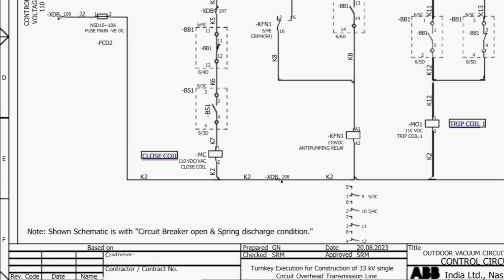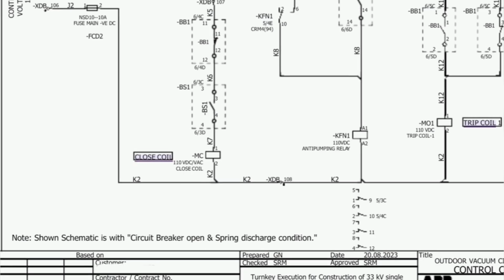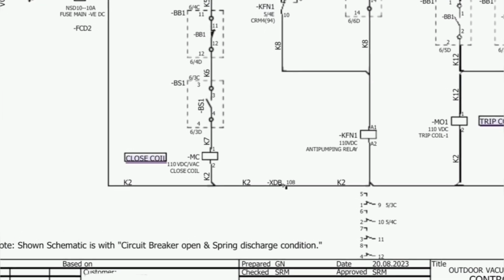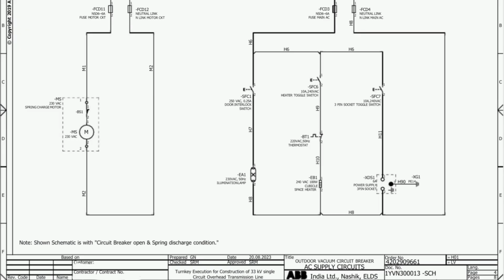Always study the drawing with the circuit breaker in the open position and the closing spring discharged. Keep in mind that terminal numbers and wiring arrangements may vary depending on the breaker model and project specifications. With that said, let's begin.